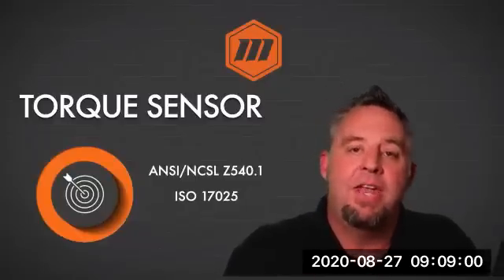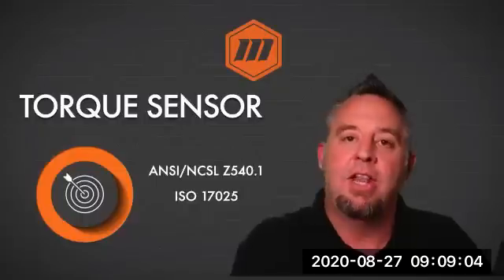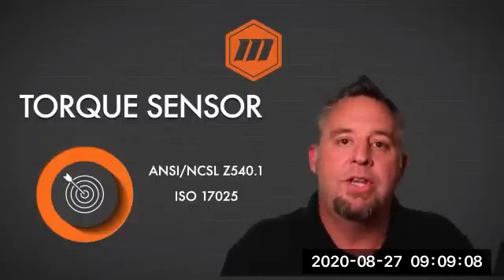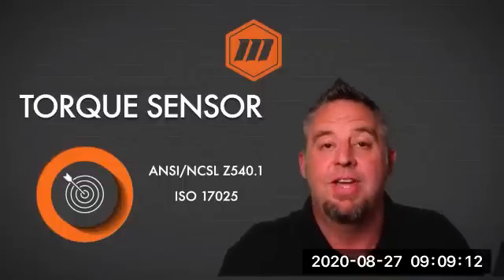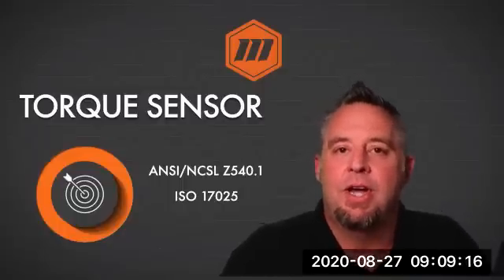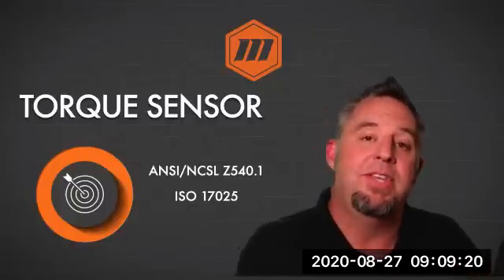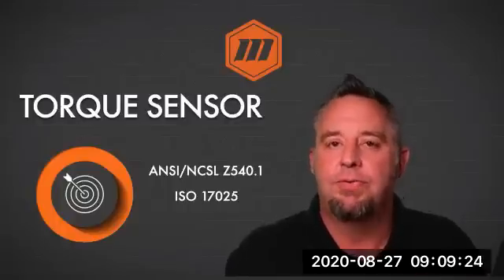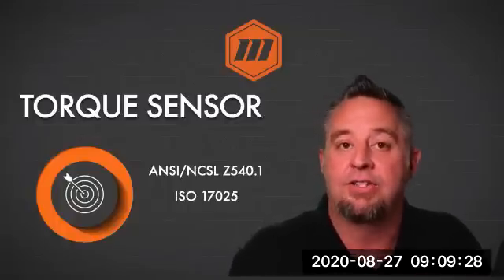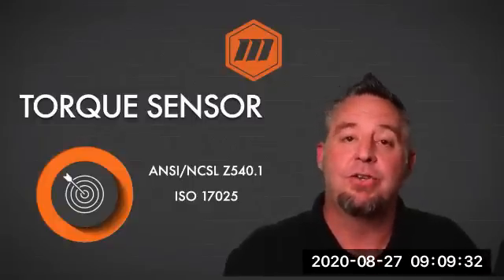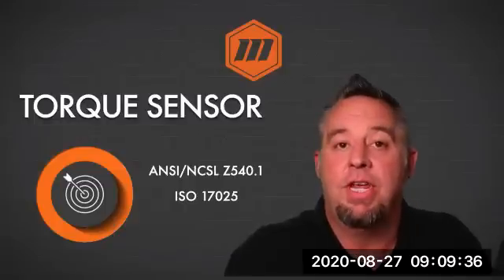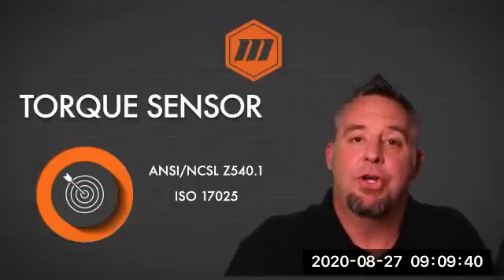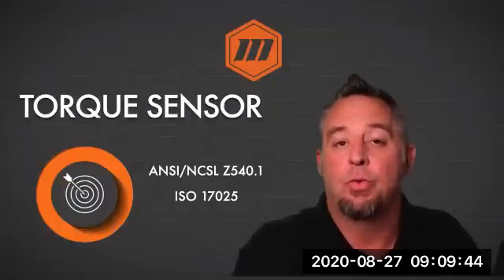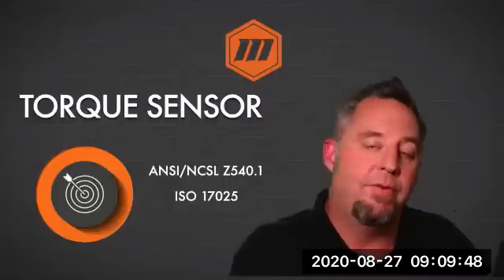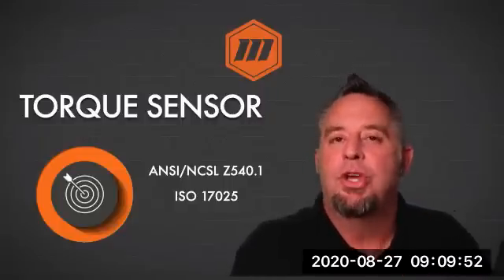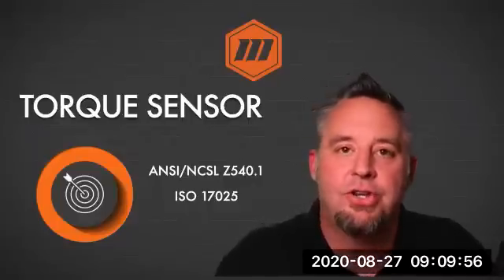But when that sensor is then paired with an analyzer, that accuracy statement changes to plus or minus 0.5% of reading. And the calibration that is done with the analyzer and the sensor is under the Z540.1 and ISO 17025 standards. So there's a big difference between an accuracy statement of reading and one of full scale. Full scale means you take the largest value of the sensor and apply the plus or minus, and that gives you that variance throughout the entire range of the sensor. If it's of reading, that's different. You take the plus or minus from the actual reading, at 0.5% for 20 to 100% of the scale. So you get a much better accuracy statement when the sensors are paired to an analyzer.